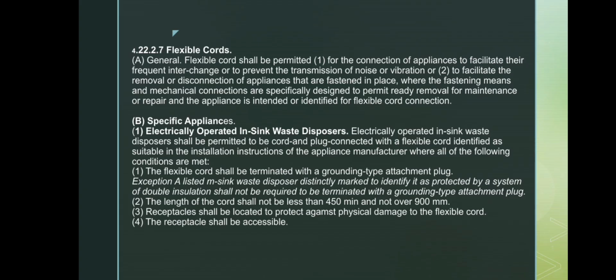The cord length must be between 450 mm and 900 mm. Number 3. The receptacle must be positioned so the flexible cord is protected from physical damage. And number 4, the last, the receptacle must be accessible.